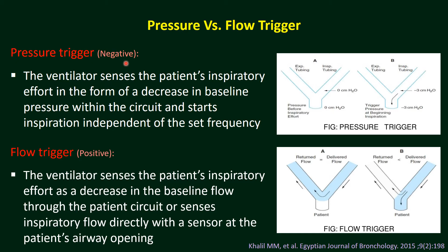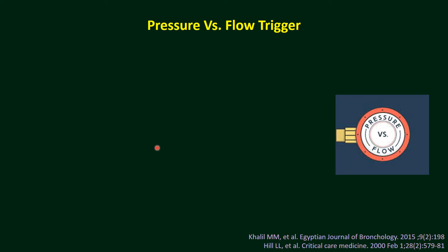So, which one will you use, pressure or flow or both? You cannot use both, either pressure or flow trigger. Most of the literature says flow trigger is a little more sensitive than pressure trigger. So, if your ventilator has both pressure trigger and flow trigger, then it is better to use flow trigger. But in older versions you may not have flow trigger and you will have to use pressure trigger only.